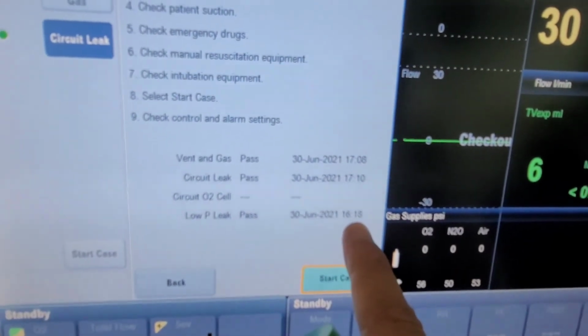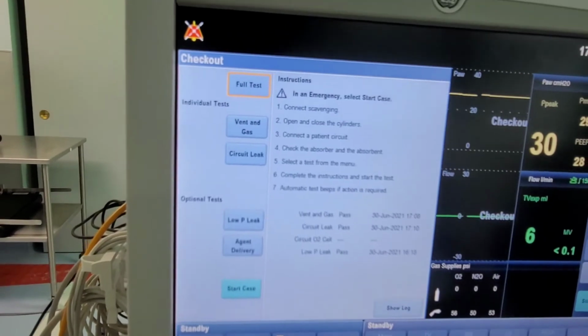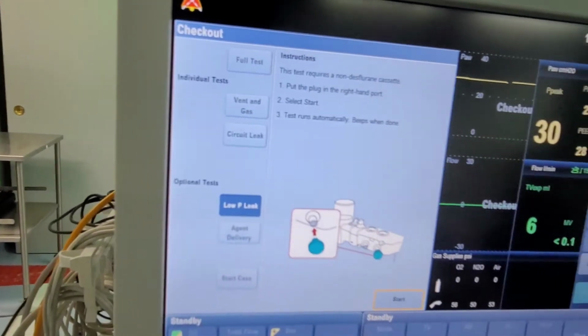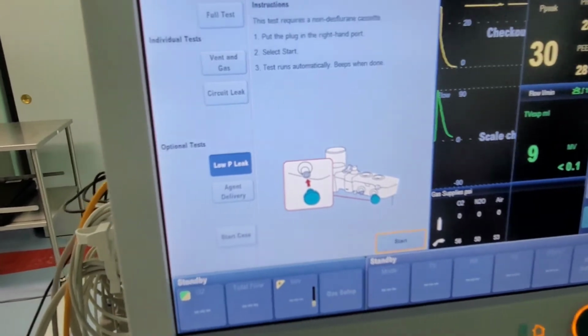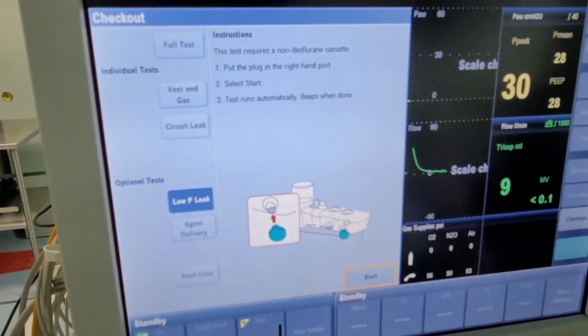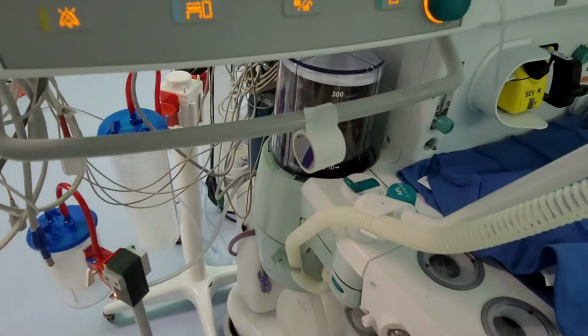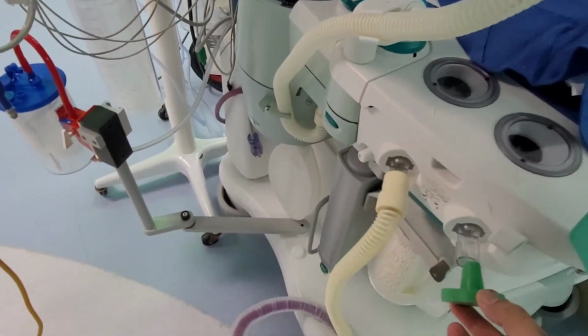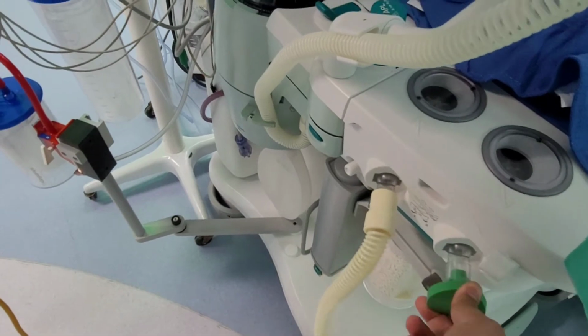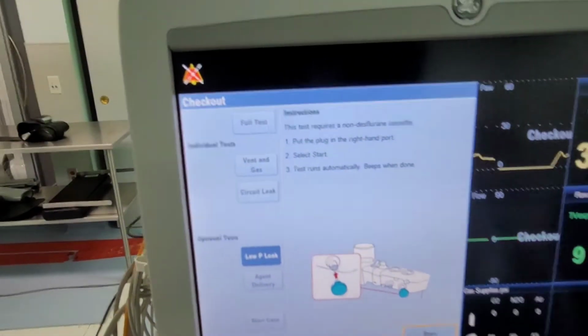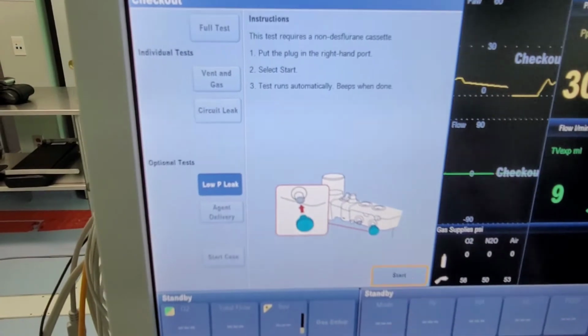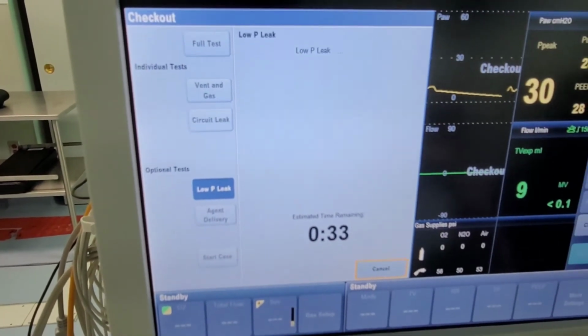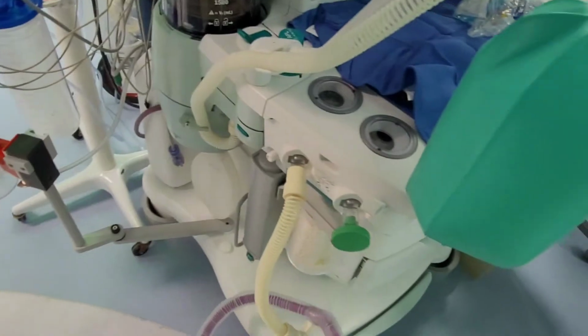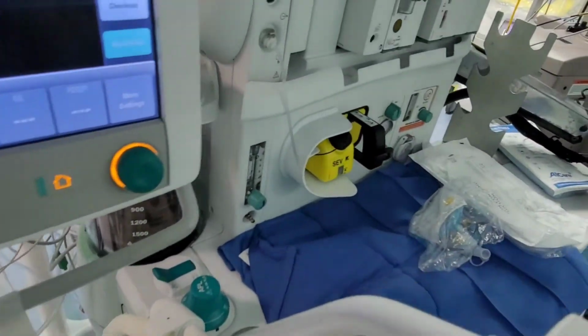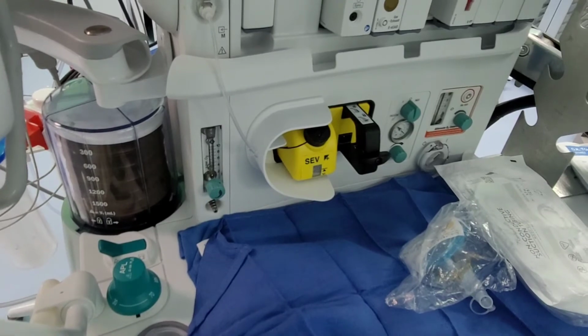Same thing, circuit leak, and a low P leak. We'll do the low P leak right now. Press back, low P leak, and follow the instructions. Get the green plug, plug the right hand port, and twist it in there. The test runs automatically, so press start. It doesn't take too long. It's going to pressurize from the right hand port all the way to the gas bench, to where the vaporizer is.